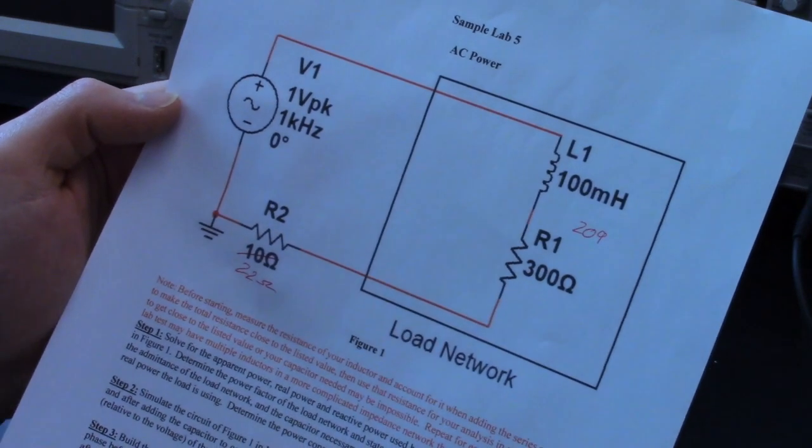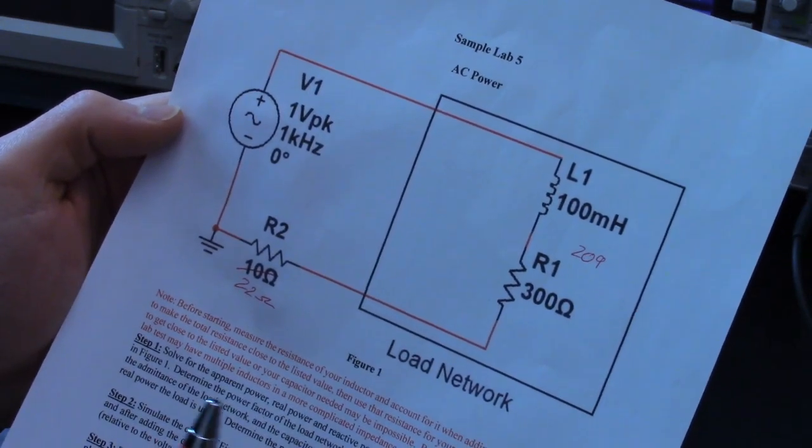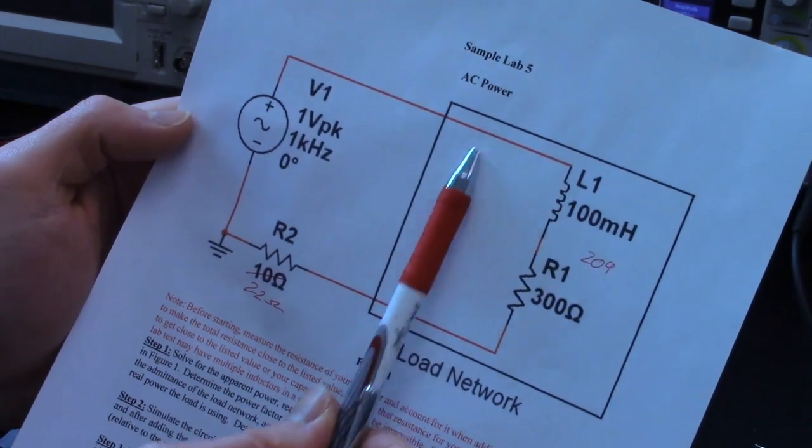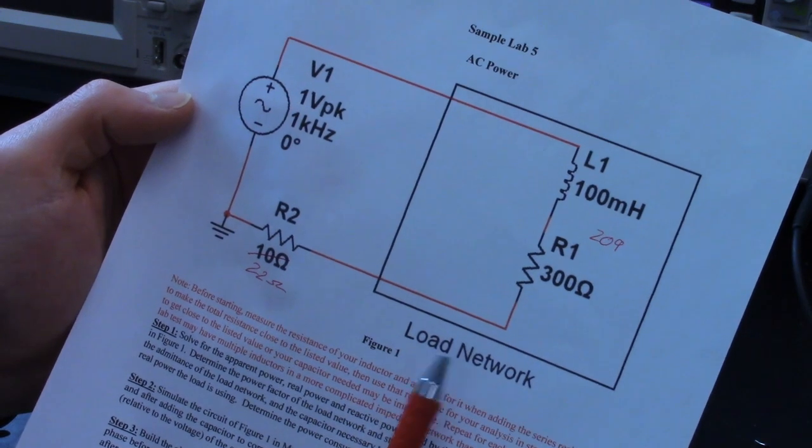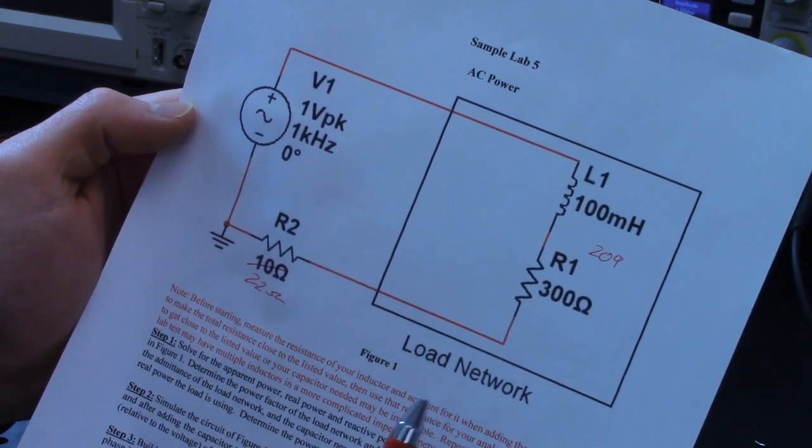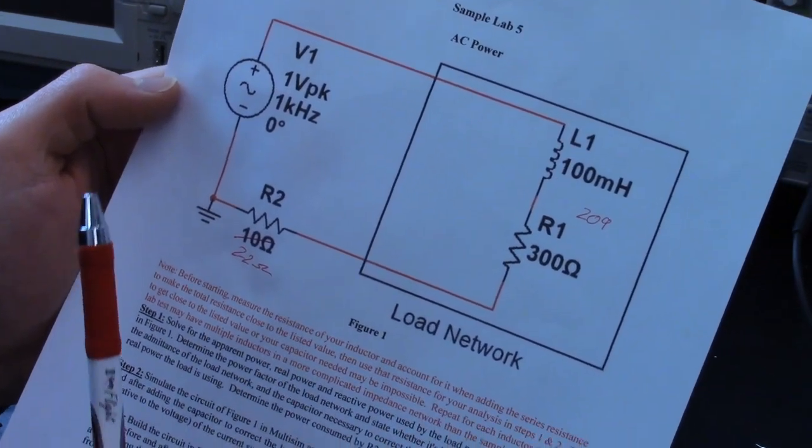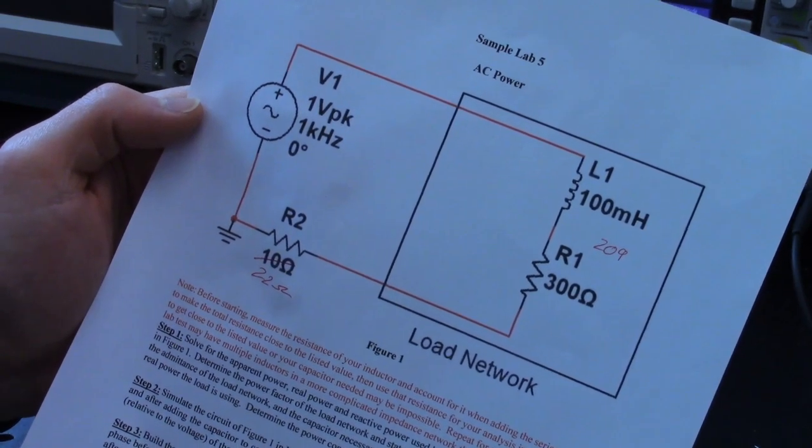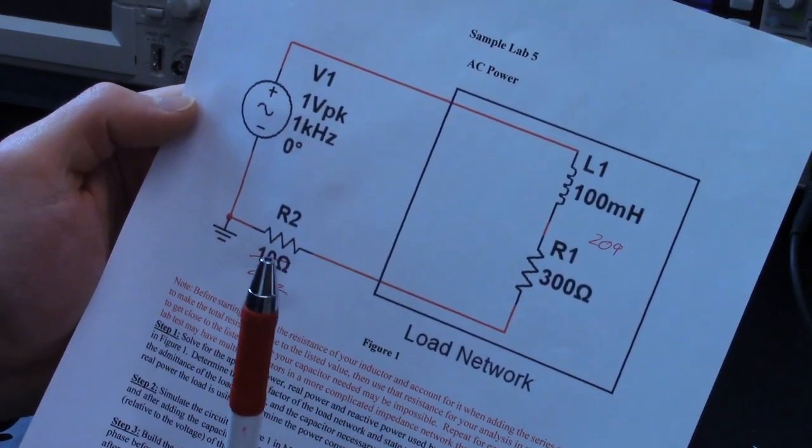Our goal is to figure out how much power is absorbed by this load network, both the real, reactive, and apparent power, and then figure out what capacitor to add in parallel in order to zero out the reactive power that's applied in order to unify the power factor, bring the power factor to one, so that we are going easier on the source network.